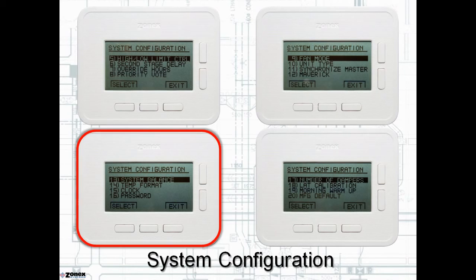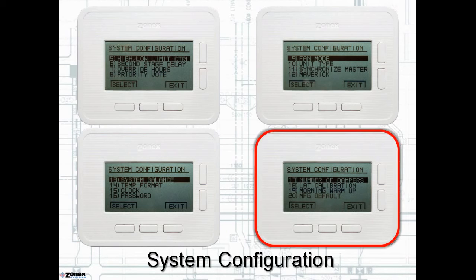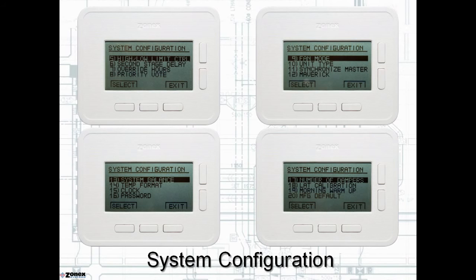The monitor provides an air balance feature to save the contractor time. With the push of a button, all dampers drive to the open position, and the fan is energized to simplify the contractor's air balance. A morning warm-up option is available. Leaving air temperature calibration, password setup and protection are all accessible from the thermostat selected as a monitor stat in your system.